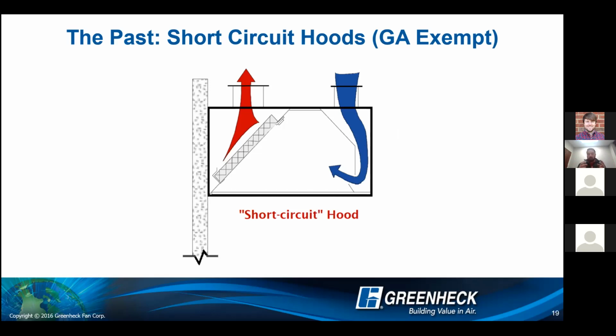It would then be quickly exhausted, which is great because that's untempered air, so it's super hot or super cold. Well, through years of study and research, what was found is that it was a good concept, but when you have 90% of your exhausted air being returned into the hood cavity, the velocity of this makeup air is so high that it disrupts the updraft velocity of the exhausted air. So it's causing air to go into that filter and cause conflation in the air, so you're losing either capture or some of that untempered air is escaping into the building. Then the building HVAC system is being taxed in order to keep that building comfortable.